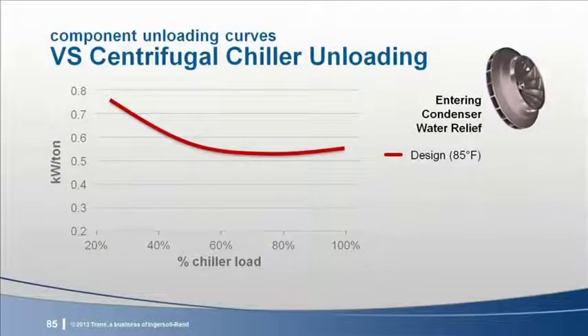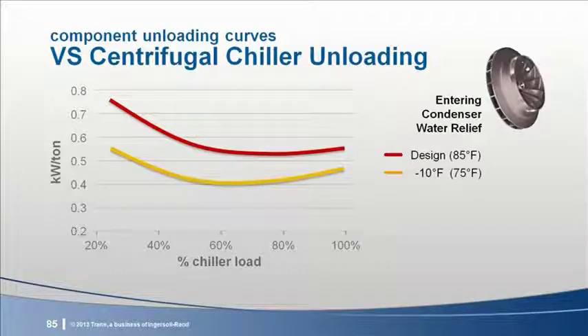The fan laws tell us why. If the compressor slows down, the impeller's ability to create pressure falls with the square of the speed. Since the condensing conditions are not allowing the chiller's lift to decrease, the impeller's speed must be kept high to meet that lift requirement. But if the cooling tower is able to provide 10 degrees cooler condenser water, the compressor can begin to leverage its variable speed capability, as shown by the yellow line.